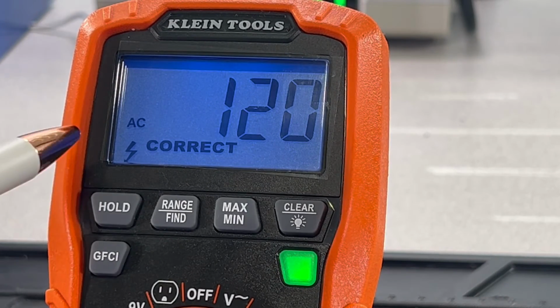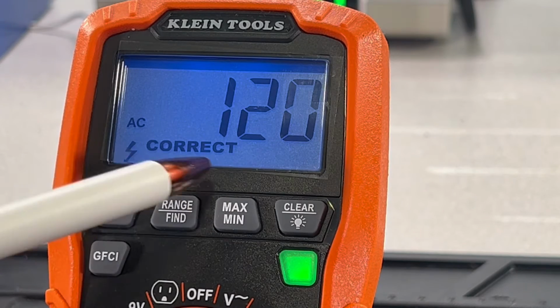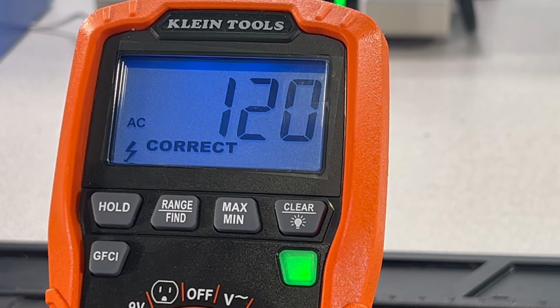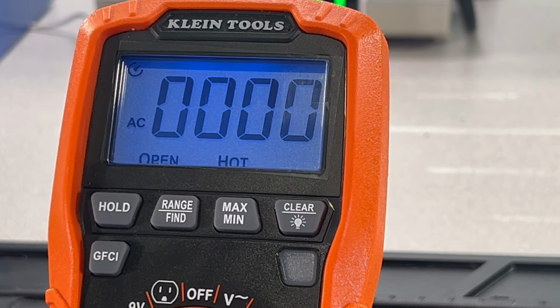But anyway, it gives you the lightning bolt to let you know that it's hot, 120 volts, and the wiring is correct. Now, if the wires were reversed, it'll display that. It'll say reverse hot neutral, or if it was an open ground, it'll say open ground, open neutral, open hot, and all that will be underneath. If I turn the power off here again, it should start saying that in a minute. It shows open hot, open neutral, reverse hot ground, reverse hot to neutral, open ground neutral, and also has the line voltage, which you just saw, no voltage, and greater than 30 volts. It has all of that.